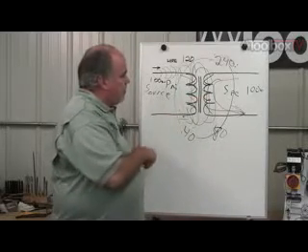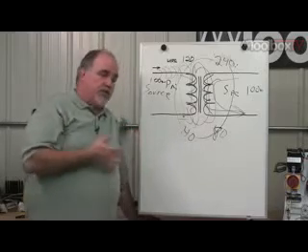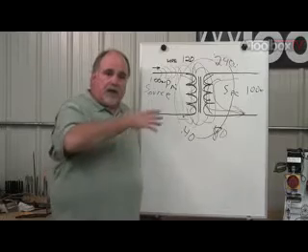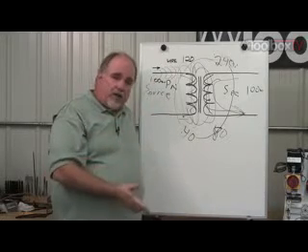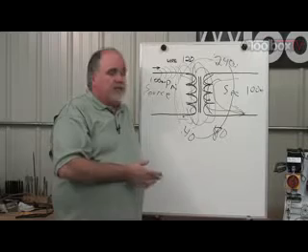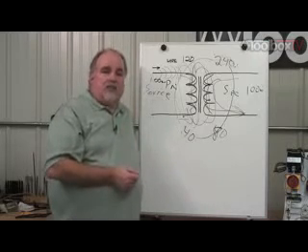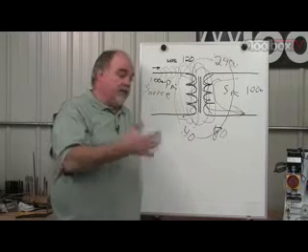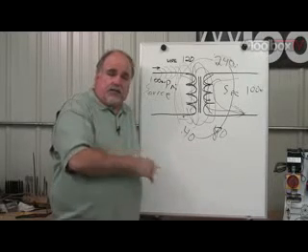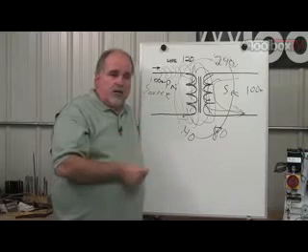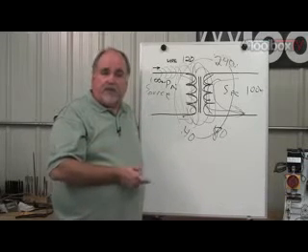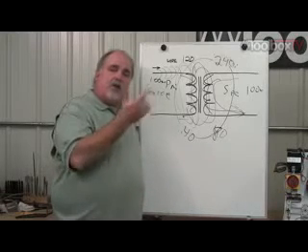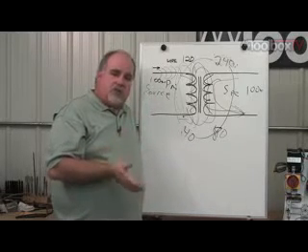This is the reason that we have power lines with extremely high voltages. Because if you've been out in the country and seen miles and miles of long high voltage power lines, the situation there is the power plants generally create AC current in the neighborhood of 24,000 volts. Right outside the generating station, they step it up in the yard. Could be up to 345,000, 500,000 volts is a common one. They step that voltage way up because the current is going to be small.